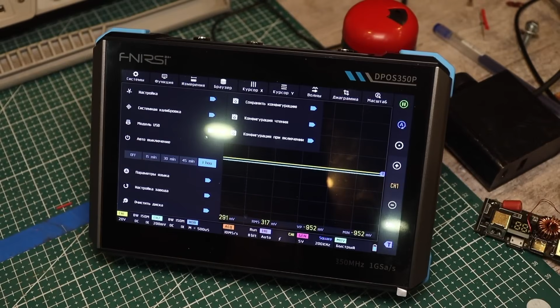Before use, you need to do two things. First, perform the calibration available here, and second, calibrate the probe. To do this, you can use the built-in generator that's provided, meaning you can use it as a reference. You need to set a square wave with a frequency of 1 kHz and feed it to the oscilloscope input. The amplitude can be set from 1 to 5 volts. Next, for example, you can press the auto button if you don't want to mess with the sweep parameters, and the device will give you a perfect display.